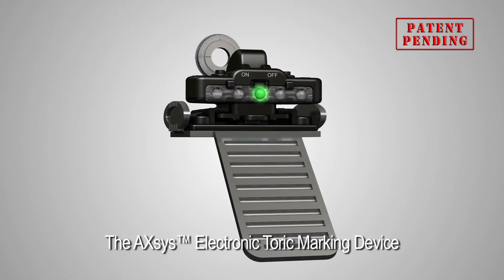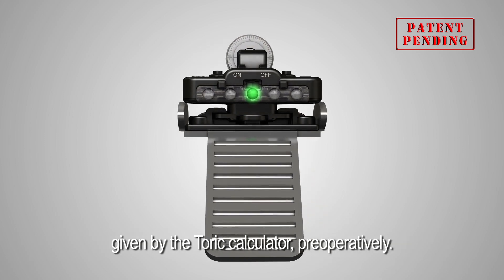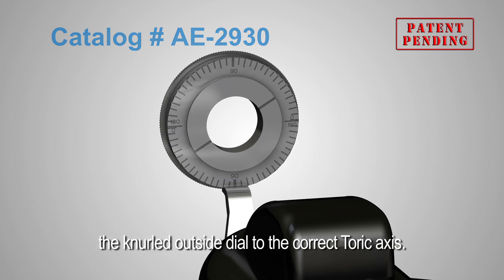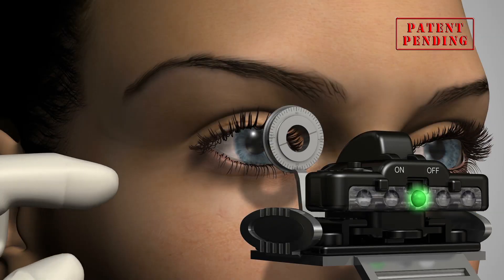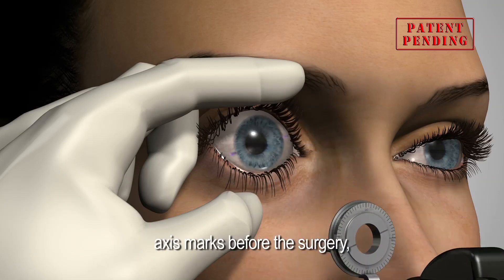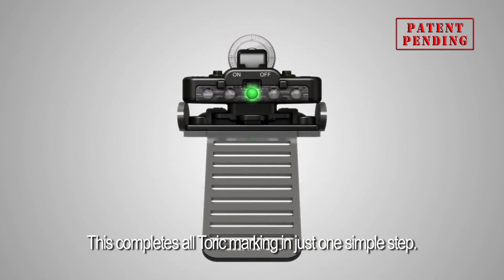The AXsys electronic toric marking device also comes in a one-step model that is designed to mark the steepest meridian axis given by the toric calculator preoperatively. The marking points can be aligned by turning the knurled outside dial to the correct toric axis. When the AXsys is held perfectly horizontal, the physician can make the steepest meridian axis marks before the surgery, as the electronic leveling device works as a 0-180 guide. This completes all toric marking in just one simple step.